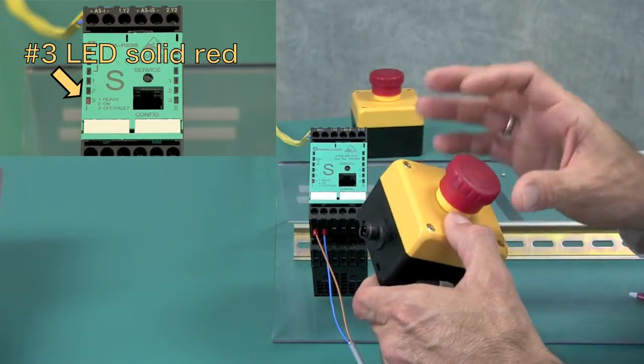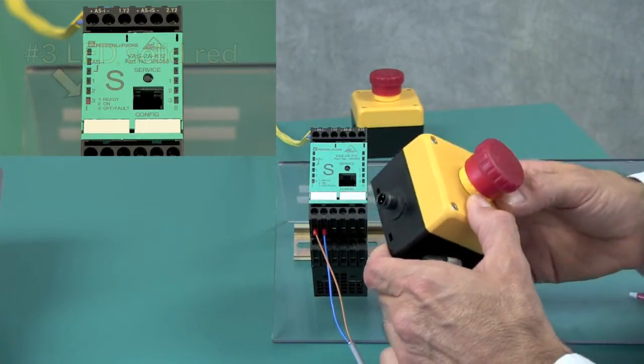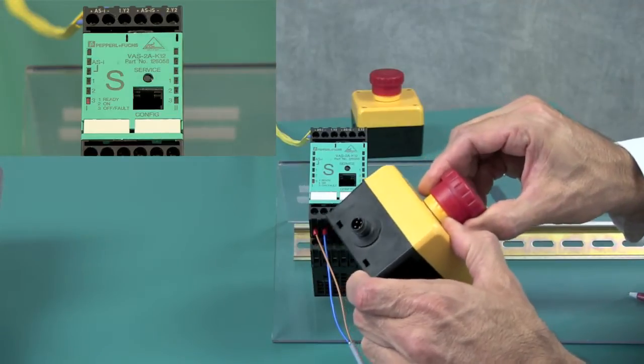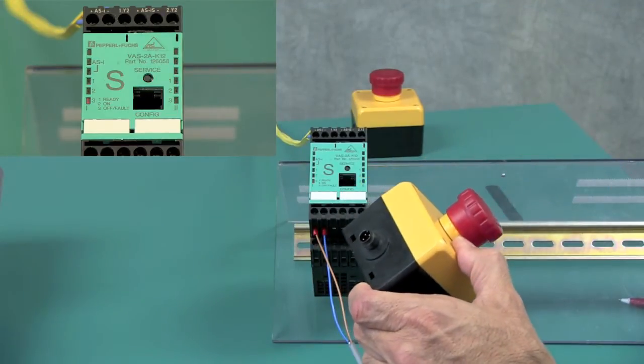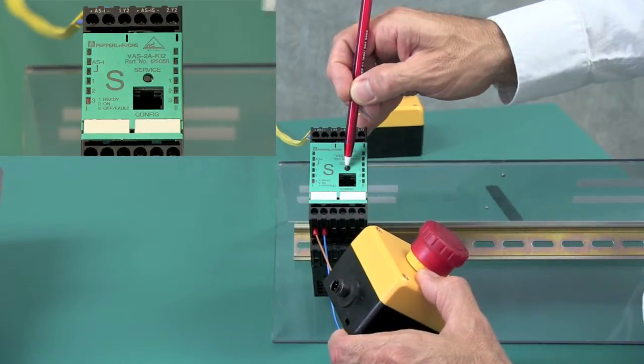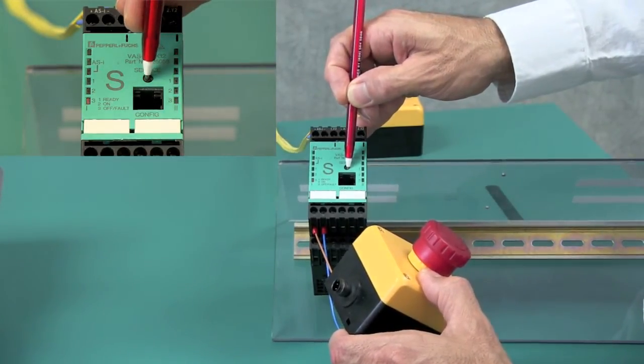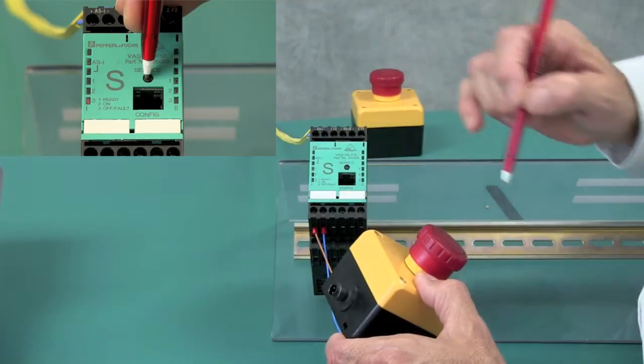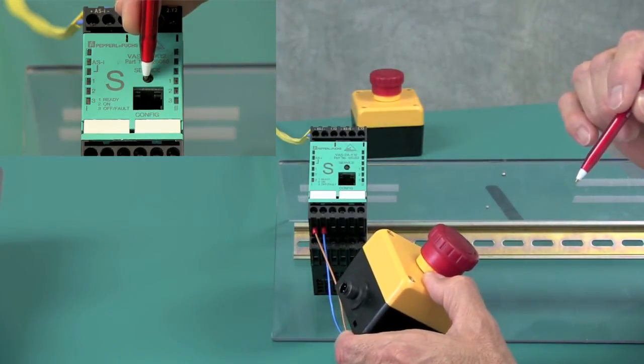This is my replacement device. It's currently at address 0 and the e-stop is in the release state. Before reconnecting, I have to push the service button lightly until the number 1, 2 and 3 LEDs are cycling through their colors.